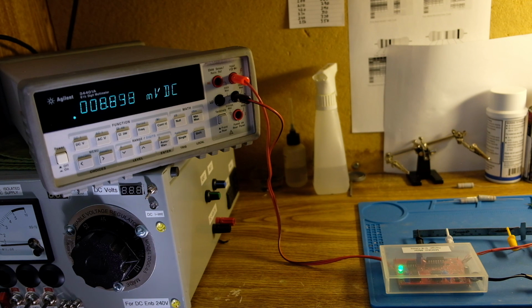This one has a limit of about 8 ohms because the supply goes to plus minus 8 volts. For me, an 8 ohm full scale for a milliohm-meter is a good compromise for measuring low value resistances. Anything higher, I can use a benchtop multimeter or even a handheld, which can do a better job in the tens, 100 ohms, and even higher.